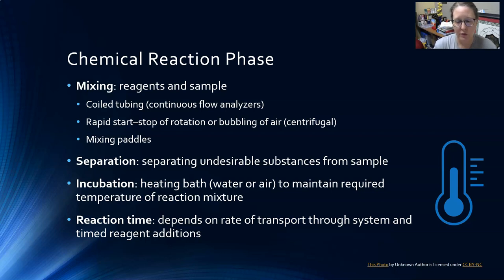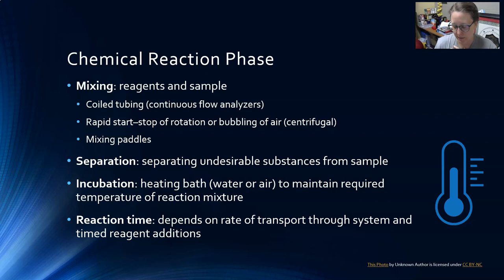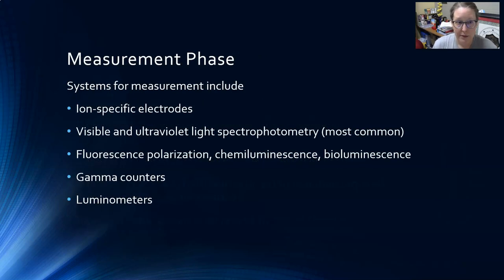The reaction time depends on the rate of transport through the system, the timing of reagent additions, and other factors. The onboard computer times everything so that vessels can enter the detection modules in sequence, getting the most efficient use of all resources and time. The machine times what is going on — when things are added, when things are incubated, and when things are read.